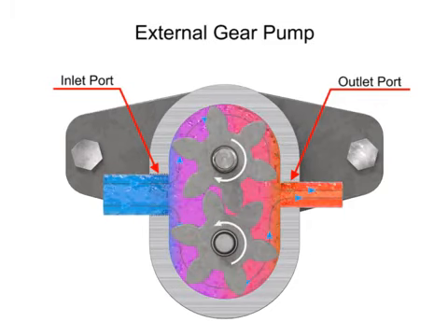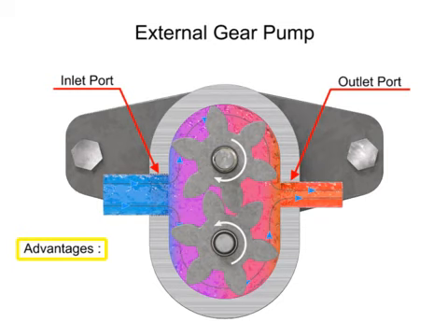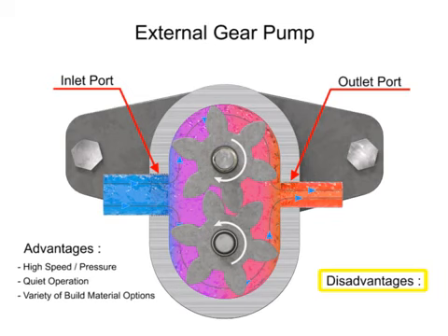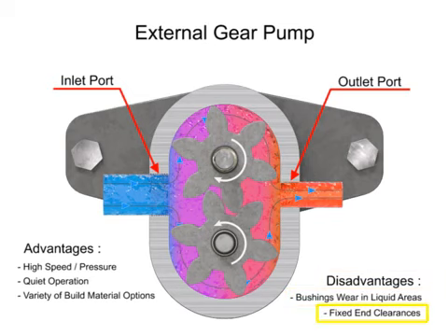The advantages of external gear pumps are their high speed and pressure, relatively quiet operation, and a design that accommodates a wide variety of materials. Disadvantages include bushings in the liquid area that can become worn, and fixed end clearances.